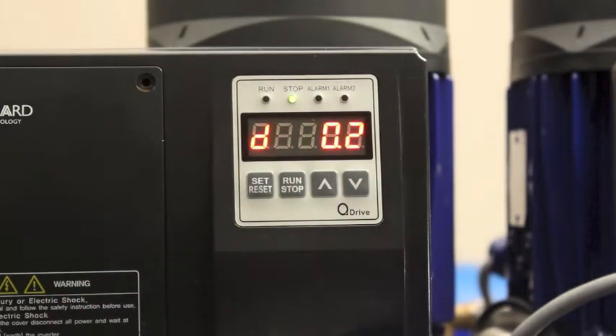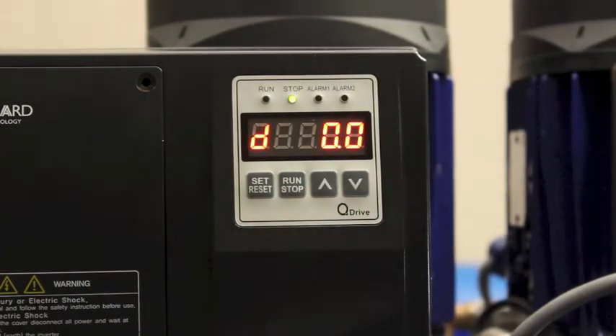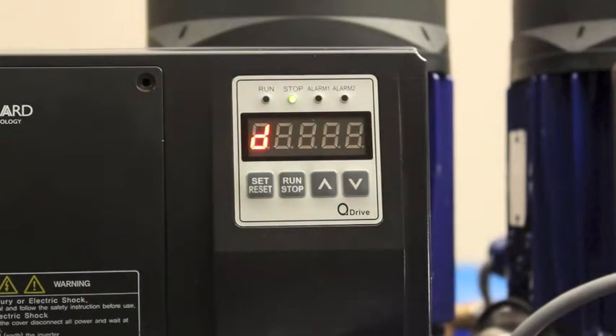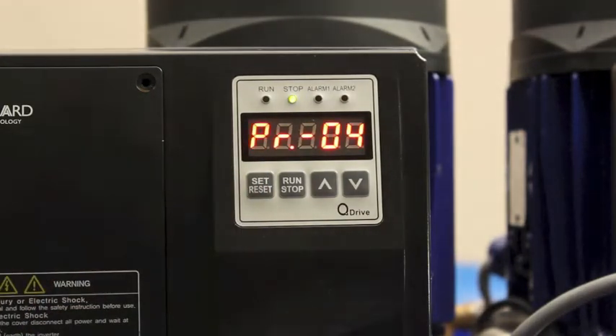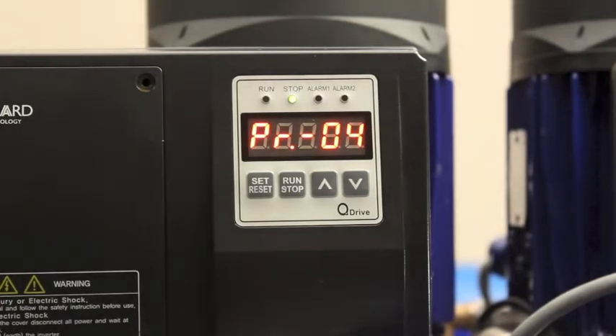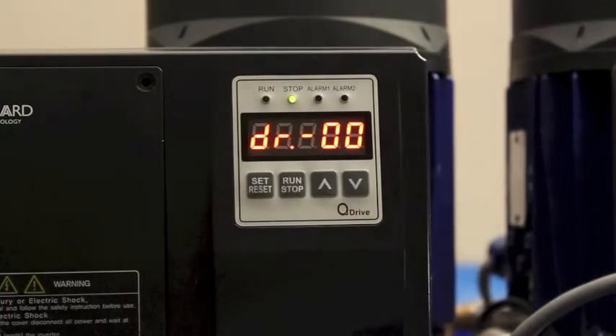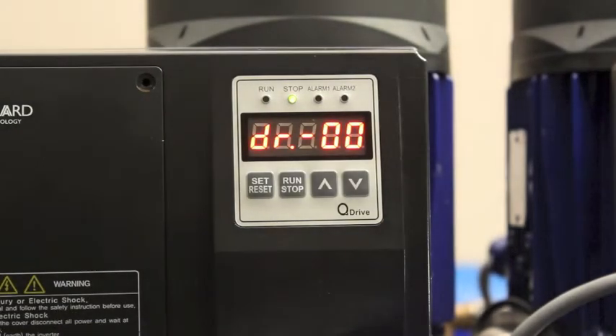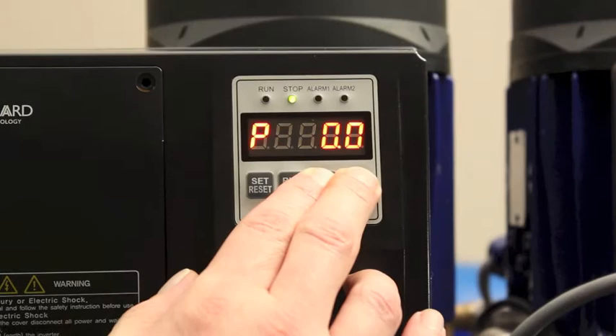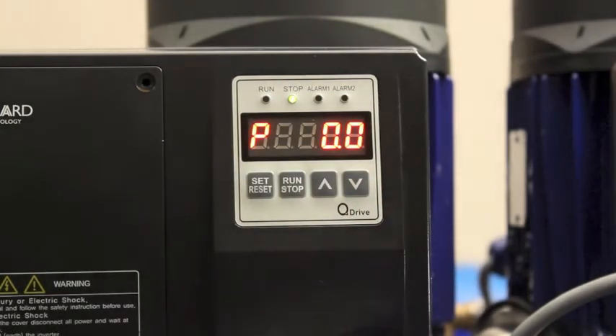Now D will flash on the left of the display and a numeral will be shown on the right. Adjust by the desired amount as noted earlier. When the parameter setting has been changed, press the Set Reset button for a couple of seconds, followed by the up and down buttons together for a couple of seconds. And again, press the up and down buttons together for a couple of seconds. P should now be shown in the display with a pressure reading. The pressure reading should now show 0 and the pump can be put back into operation.